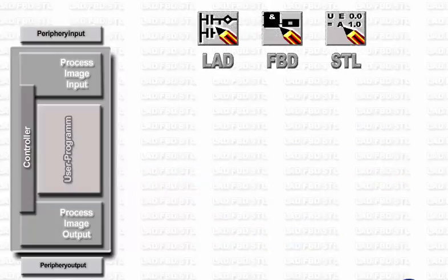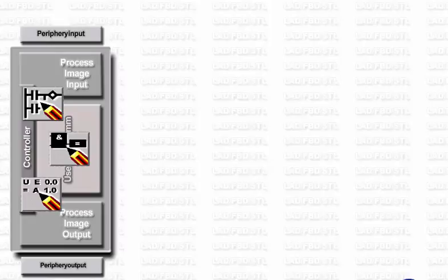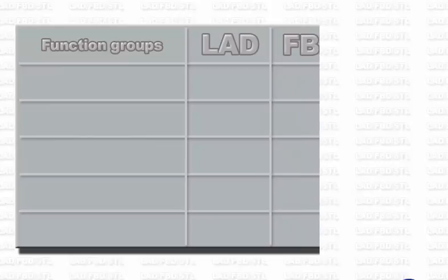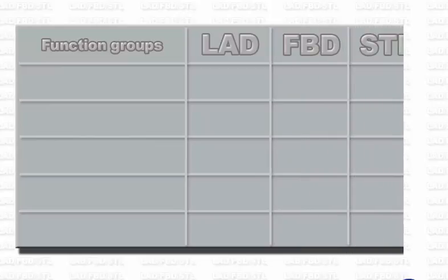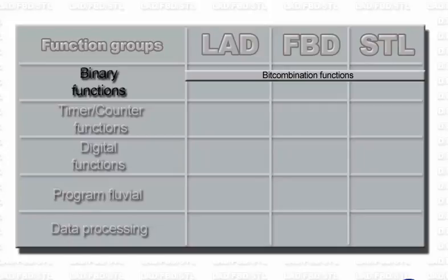Depending on the program structure and the application case, you can even mix all three languages within the same CPU. These three languages have a representation format that makes them easy to learn, but offer at the same time an extensive inventory of functions or commands which allow you to handle almost any typical automation task. Several function groups are distinguished depending on the task in hand. In the function group of binary functions, all combination tasks can typically be resolved with binary operands. Special commands such as edge detection help to speed up the execution.